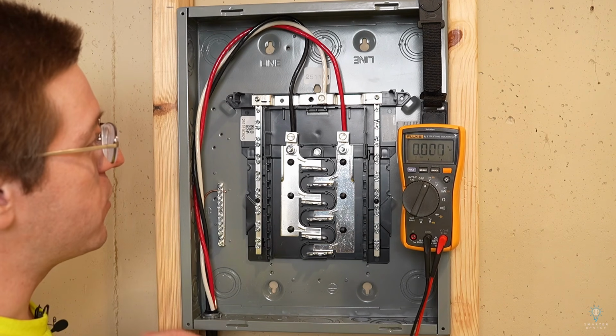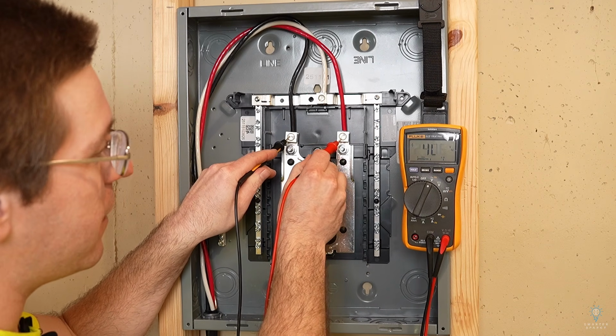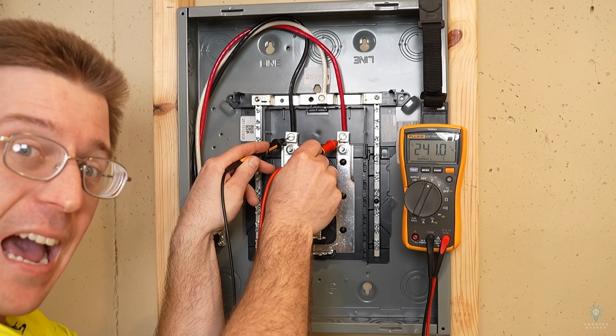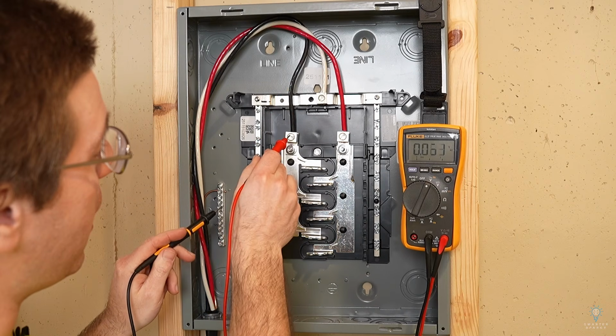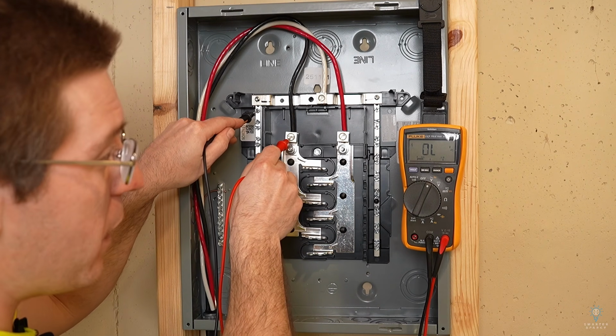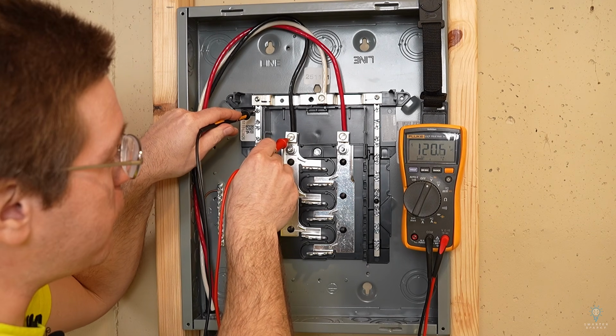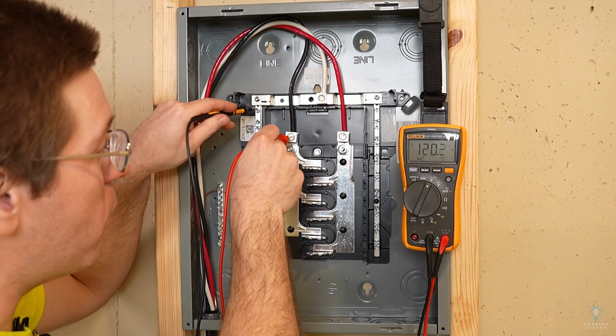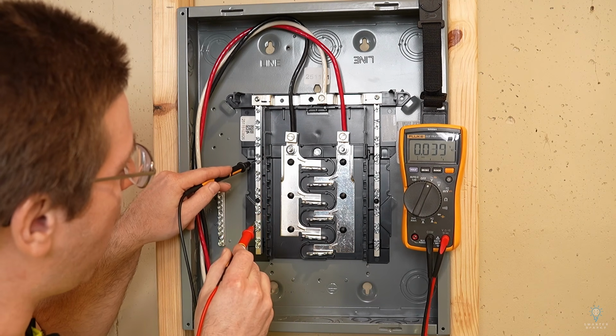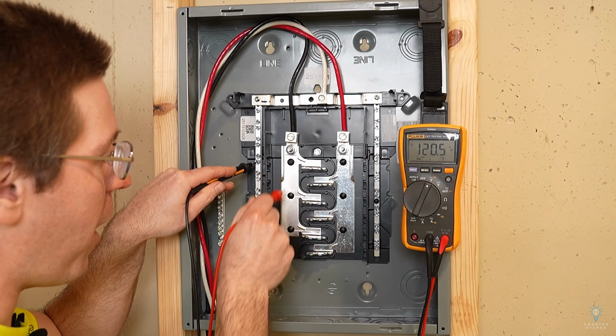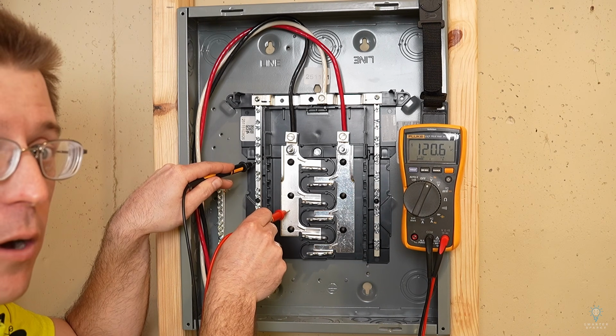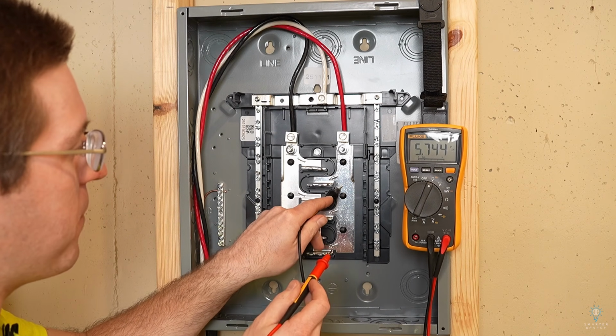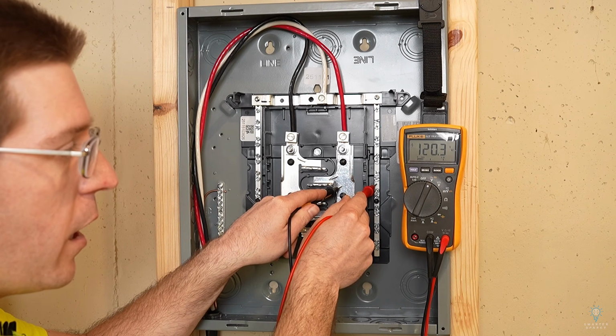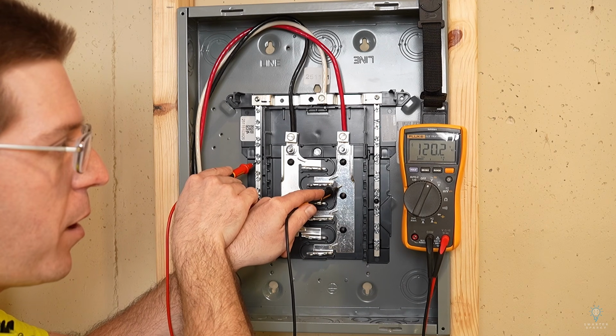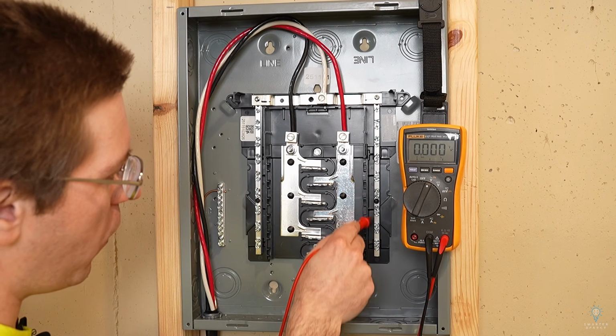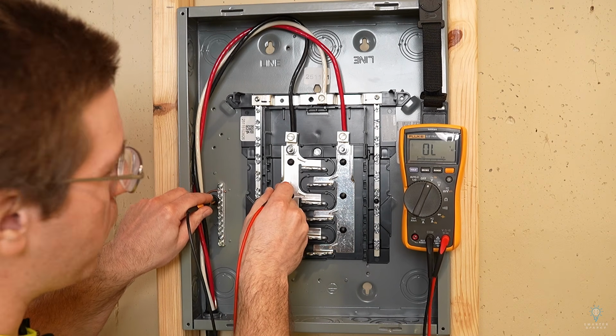So let's take some voltage measurements real quick. If we measure from line to line, we get 240 volts, just like we would have in our main electrical panel. If we measure from our line to neutral, we get 120 volts. So just like in the main electrical panel, if we wanted a 120 volt load, we would feed it from one breaker and the other end would go to neutral, because this whole bus bar is 120 volts to ground or neutral. Same on the other side, if we measure from this bus bar to the neutral bar, we get 120 volts. It'd be the same if we came over here to this neutral bar as well, because again, that neutral bar is connected all the way up and over. It's also the same voltage if we measure to ground.